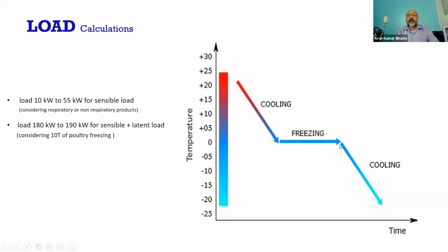And then below freezing there is another load which we call the below-freezing sensible load. So we have an above-freezing sensible load and a below-freezing sensible load, which are almost negligible in comparison to the freezing or latent heat of freezing. So I think now you can understand why the load is varying, in the same room, from 10 kilowatt to 190 kilowatt.